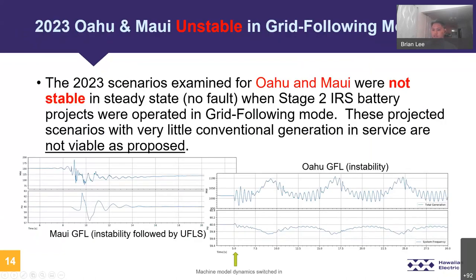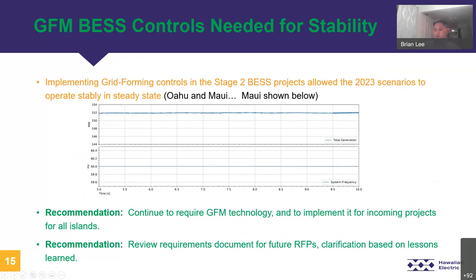So the first key conclusion of the study is that with the stage two projects in grid following mode and the level of IBR penetration, the system was not stable in steady state. Here are two plots showing just a flat line test with no fault, or N minus zero. When the dynamics were released in the EMT model, oscillations began to form. Over here on the left, we see a Maui example. Oscillations began to form and cause UFLS. In Oahu, we saw that there were sustained oscillations. However, when the stage two projects were swapped with their grid forming models, the system was stable in steady state. This plot is for comparison with the plot before, where here we see the flat line.